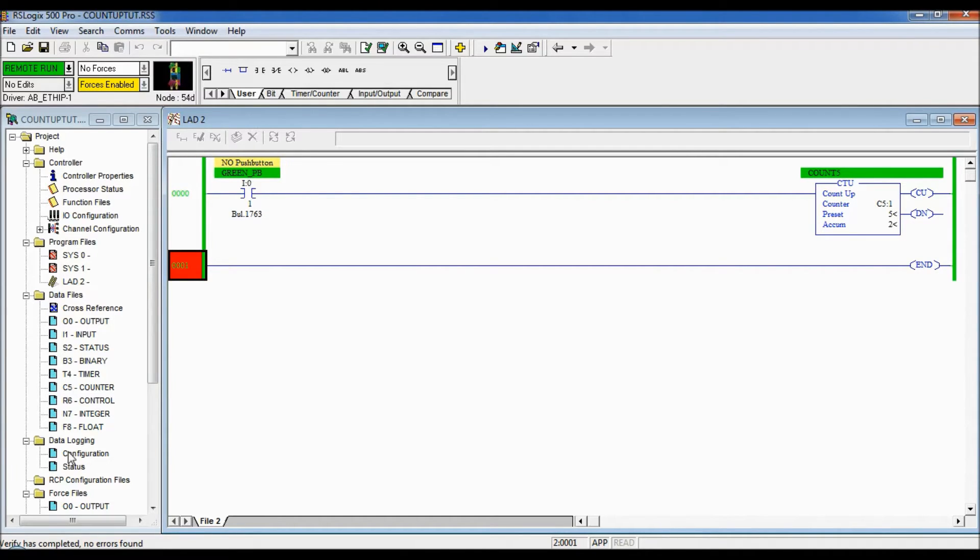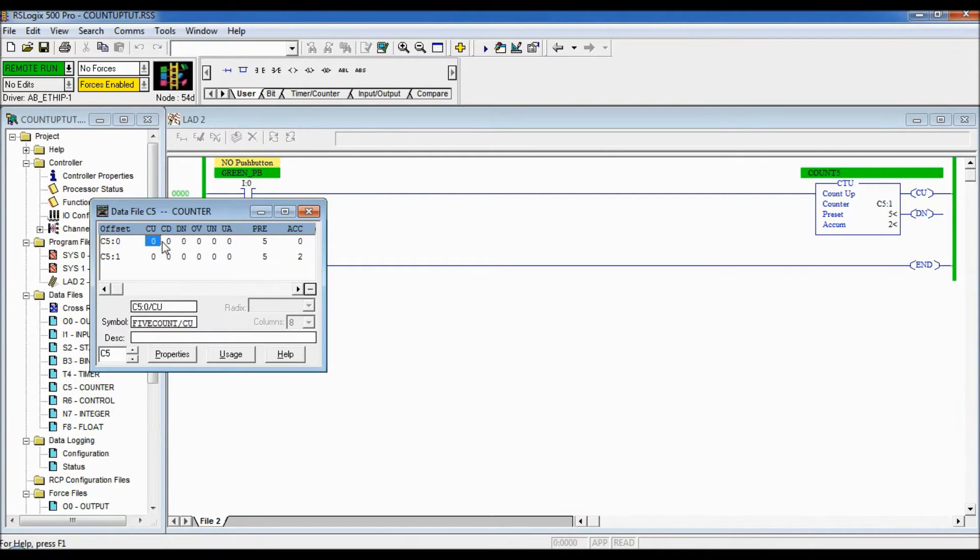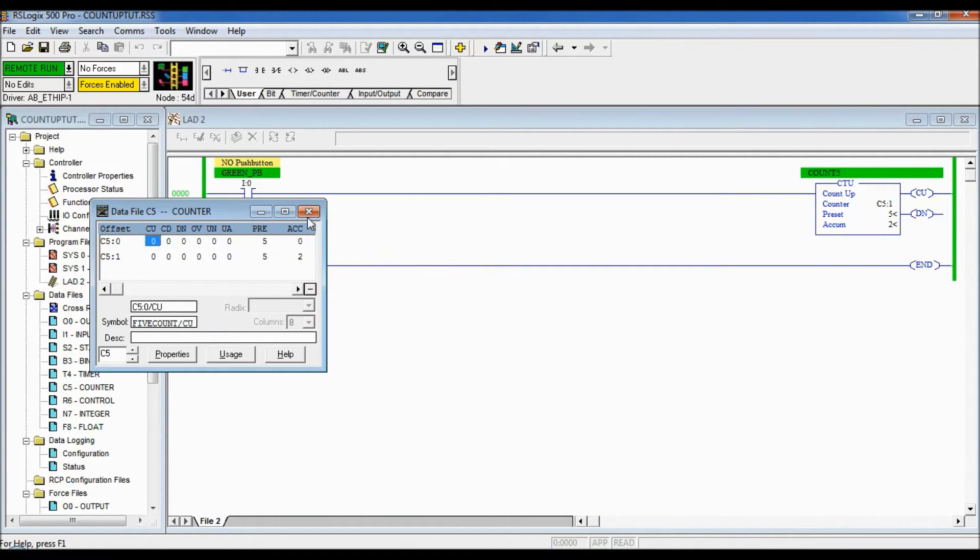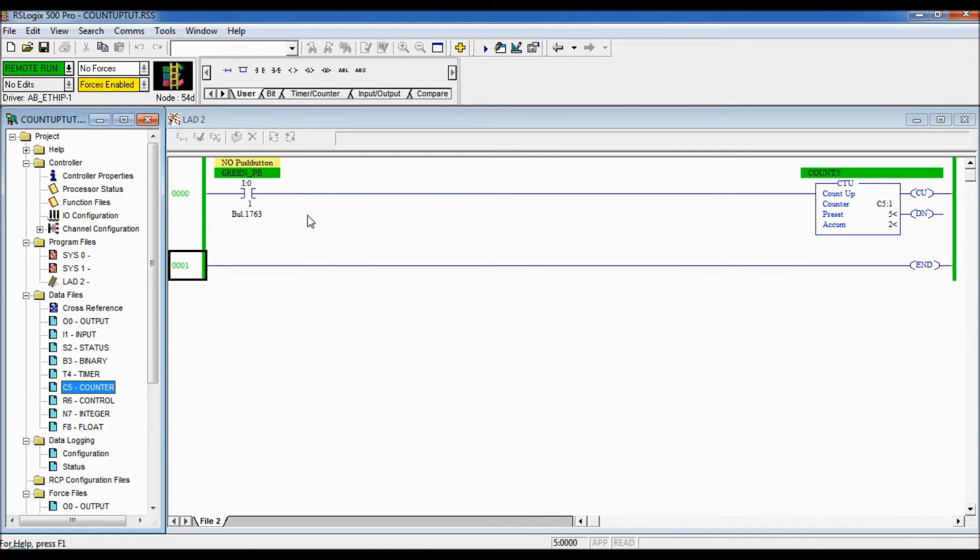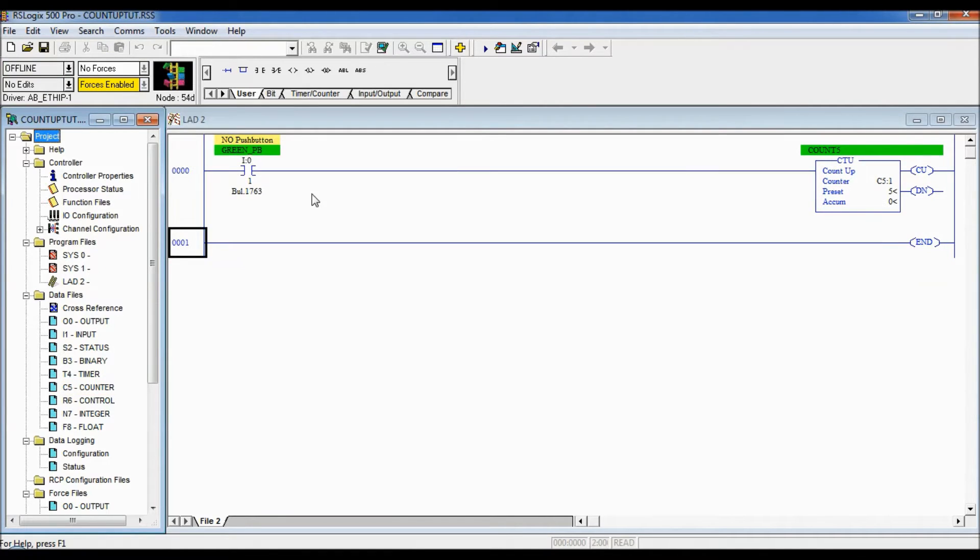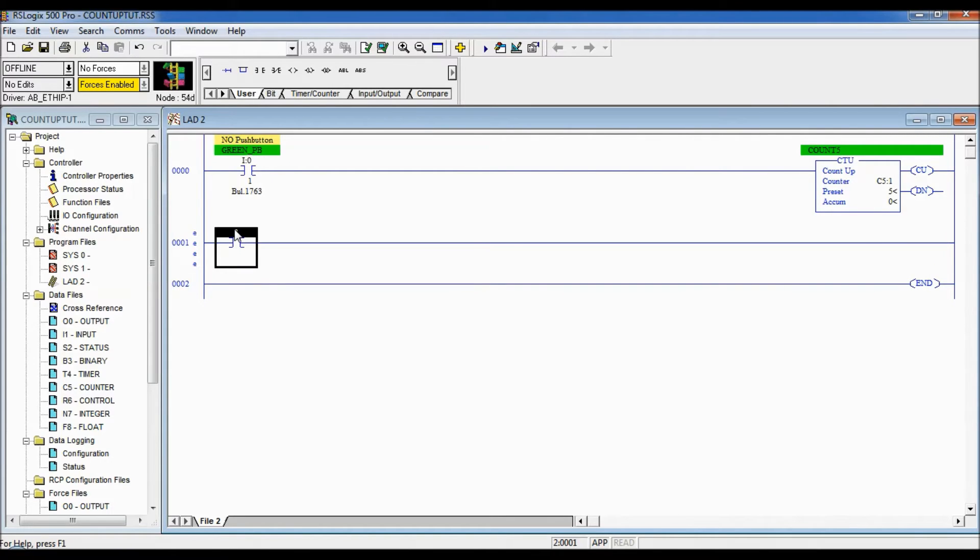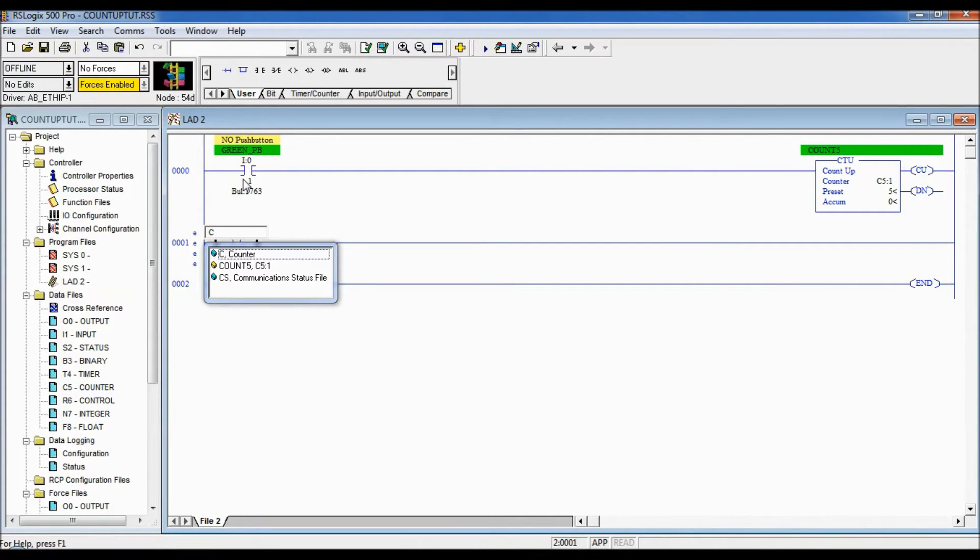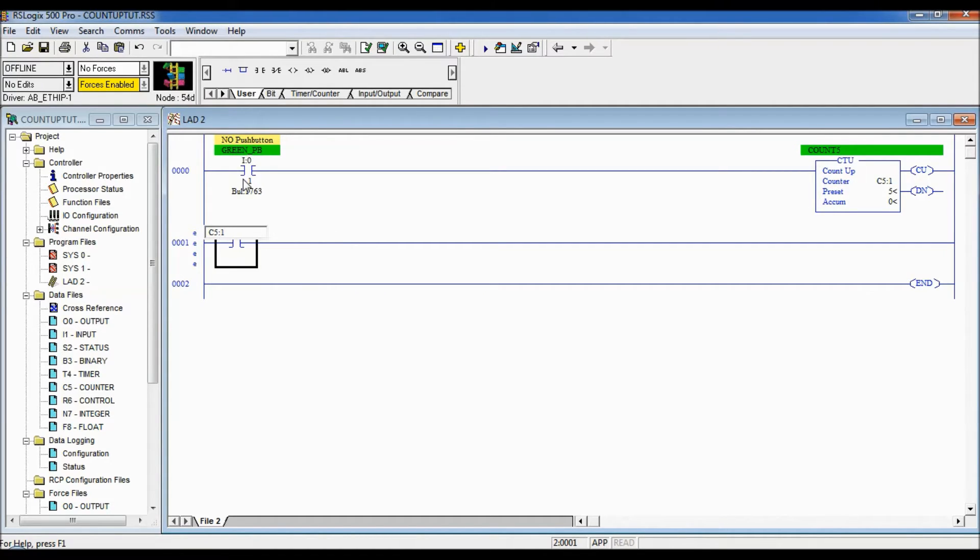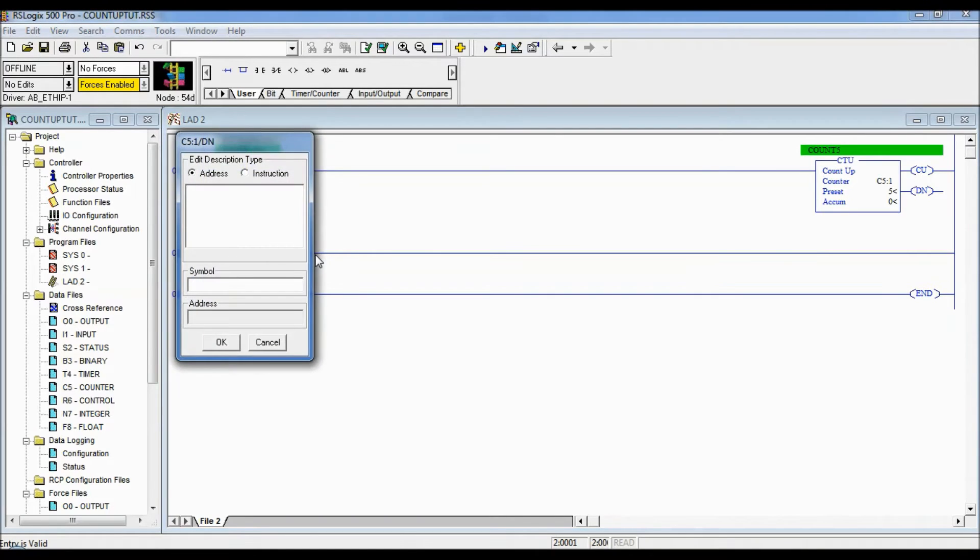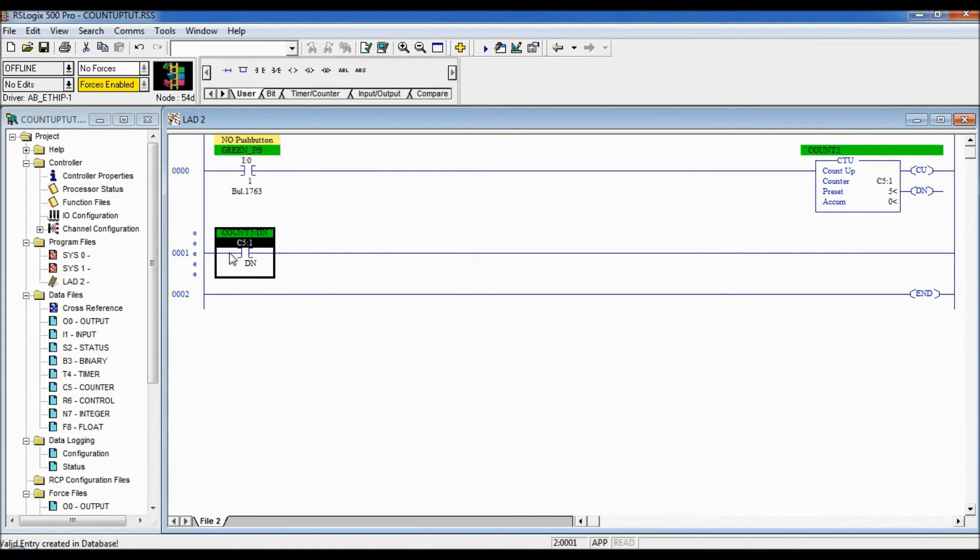So with the count up we can use the CU bit, we can use a done bit and the OV bit. So I'm gonna add that logic. The next rung I'm gonna put another rung in here and I'm gonna use our done bit. That's the most common one we're gonna use most of the time because we want something to happen when something's usually done counting. So it's C5 colon 1 and I want to address the done bit.